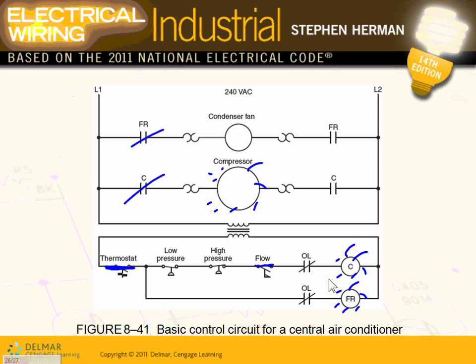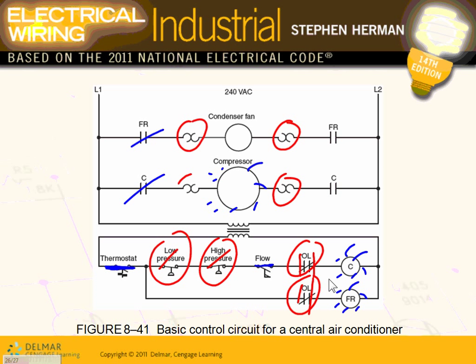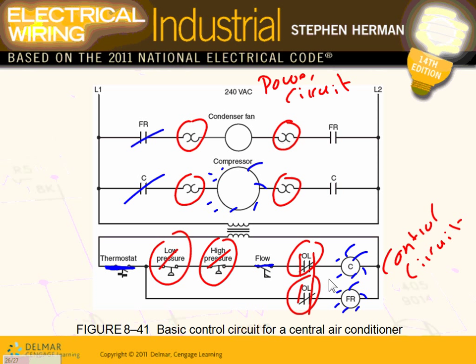If you have an overload instead of creating a bomb inside your compressor — if you have high pressure, this contact opens and kills the circuit. If you have low pressure, this opens and kills the circuit. If you have an overload condition, this opens and kills the circuit. All these devices are safety devices in the power circuit and the control circuit. This is your control circuit; this is your power circuit. Power to power the equipment, control to control the equipment.